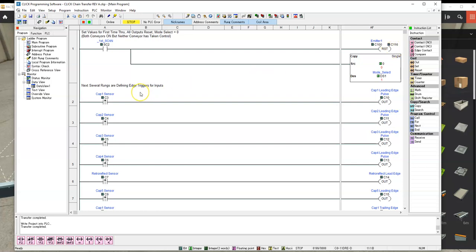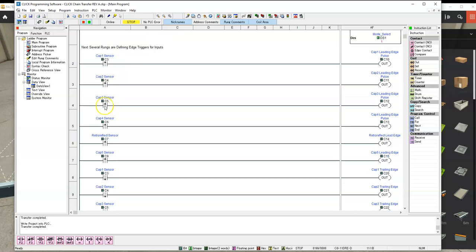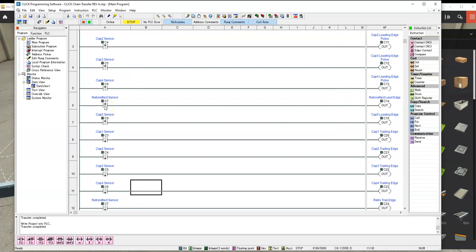One of the great features of the Click PLC is it has such easy-to-use edge triggers. We're interested in when the leading edge of the pallet is going past the sensor. So that's the transition from a low-level signal to a high-level, so we need the rising edge. But then we're also interested in the trailing edge of the pallet when it actually clears the sensor and is on to the next conveyor point, so we have falling edges too.